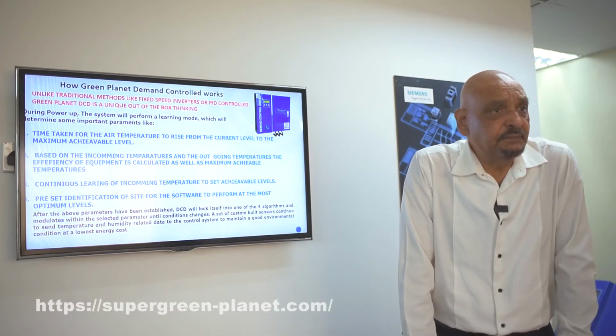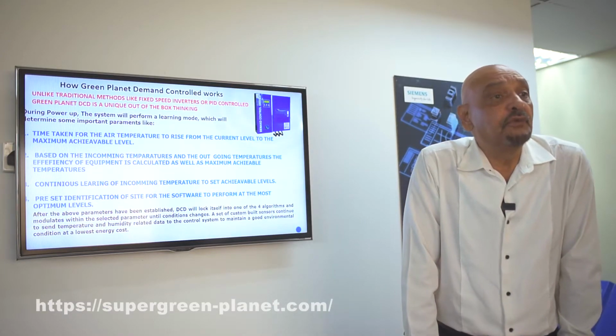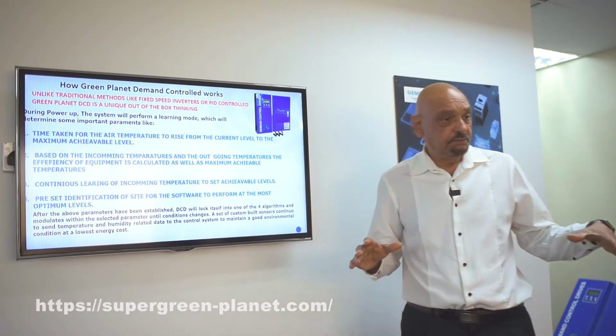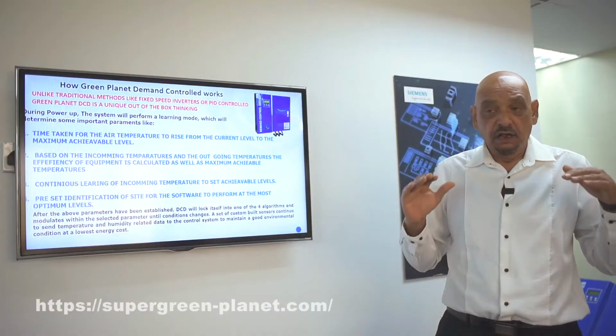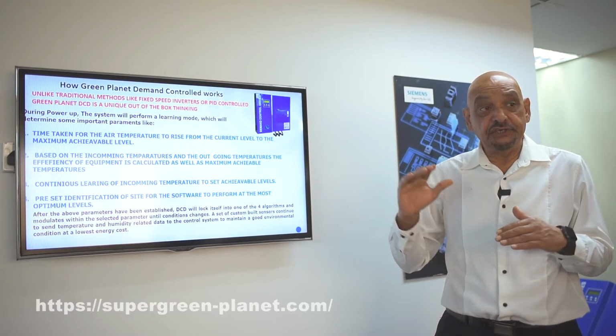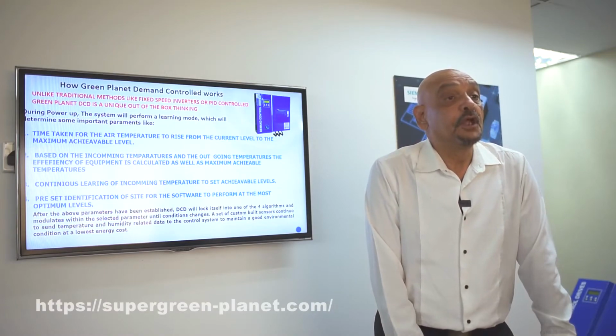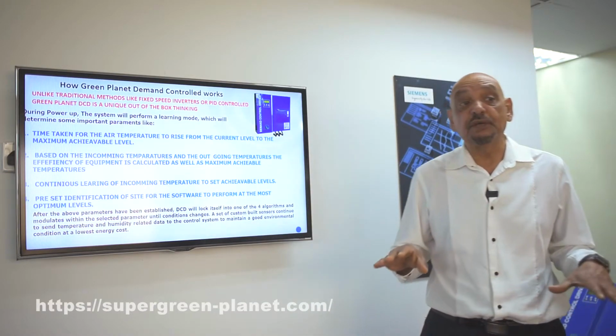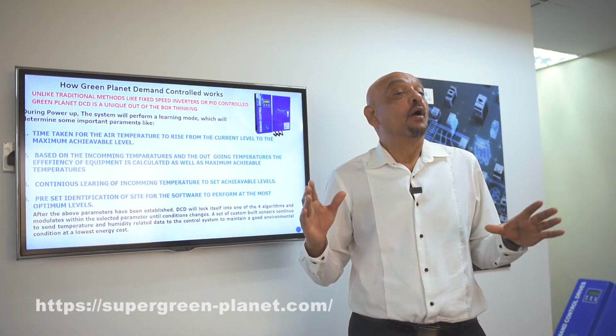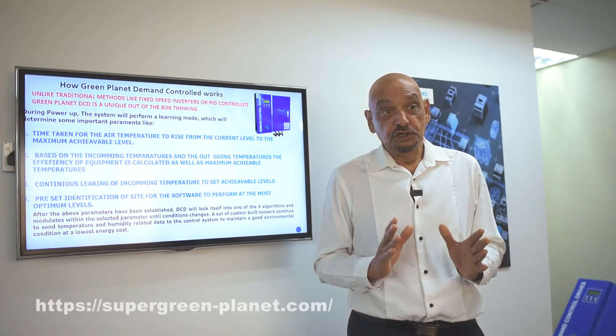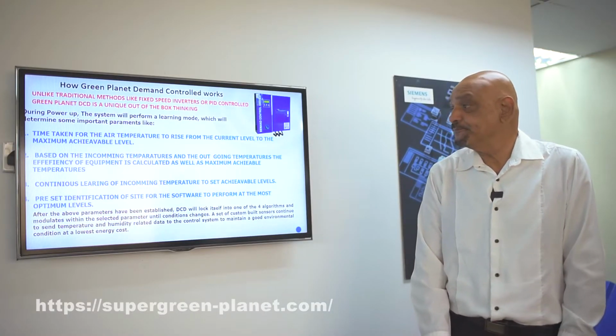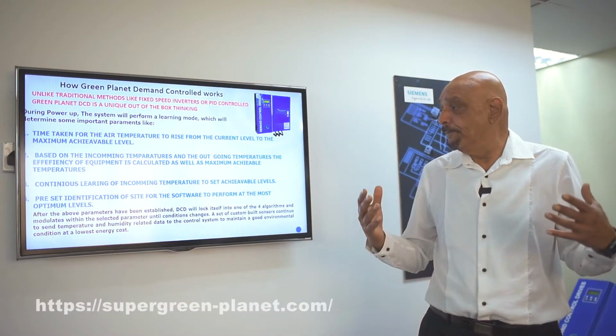After the soft starting period, you will have a certain period of learning mode. This is where the software within the system will learn, for example, how long it takes from your current level to rise to the maximum your air handling unit can achieve. This is important because the system has to calculate at later stages how soon to respond to changes in conditions within your environment. The second thing it will learn is the best your air handling unit can achieve.